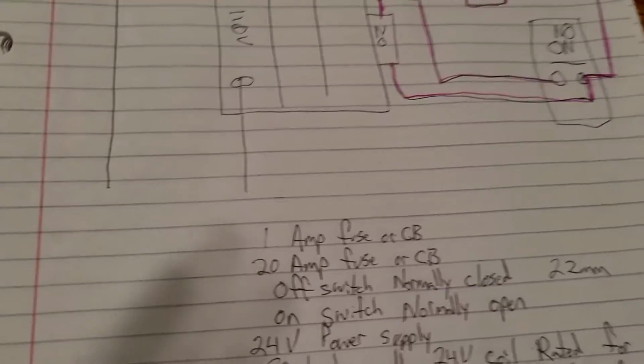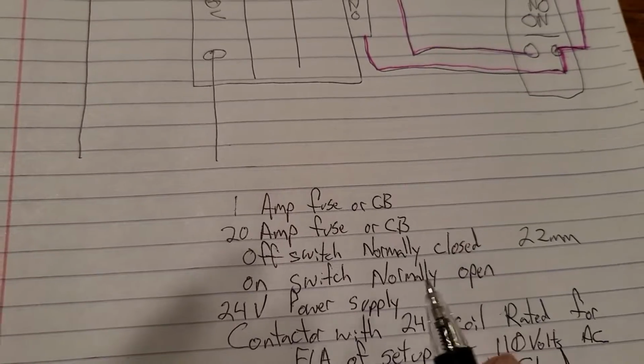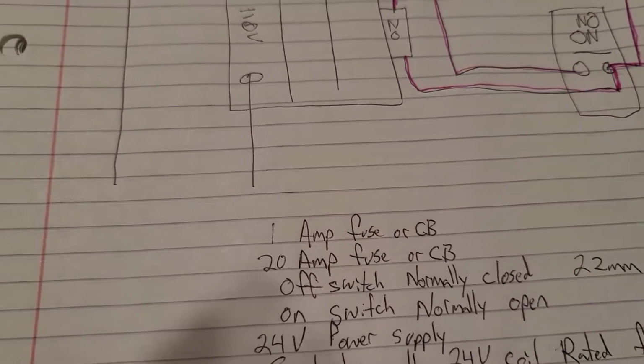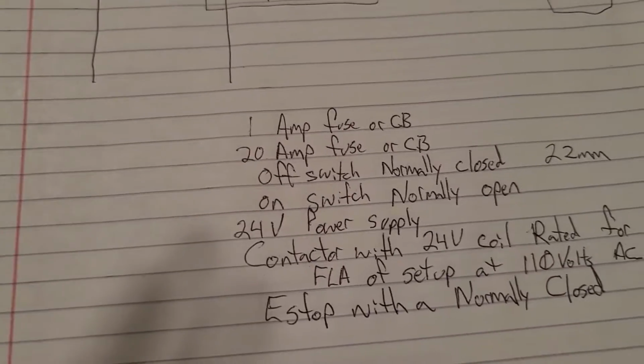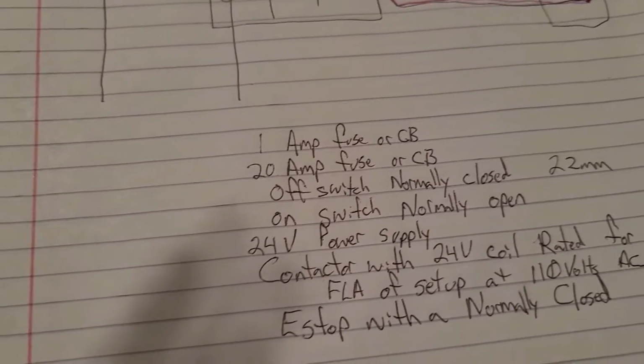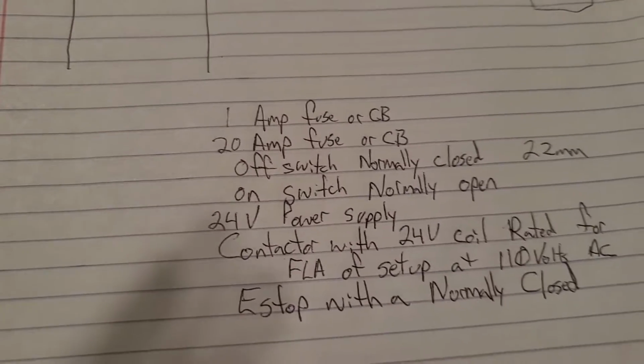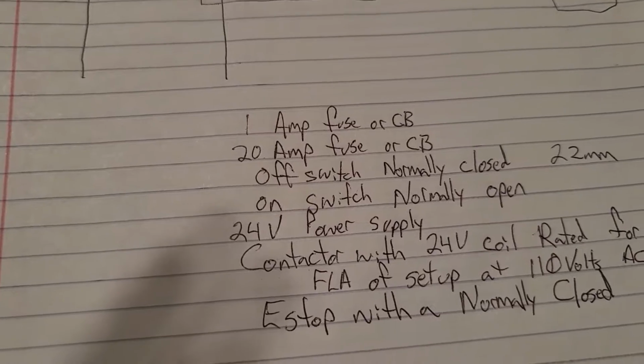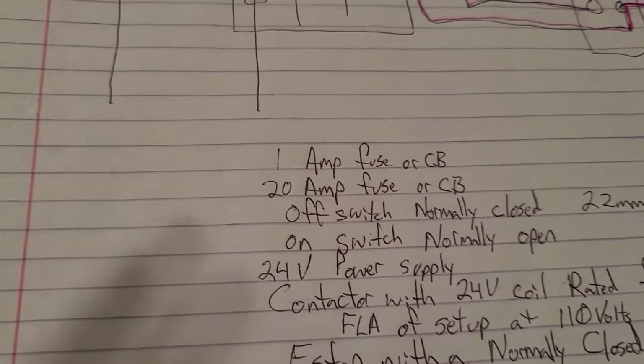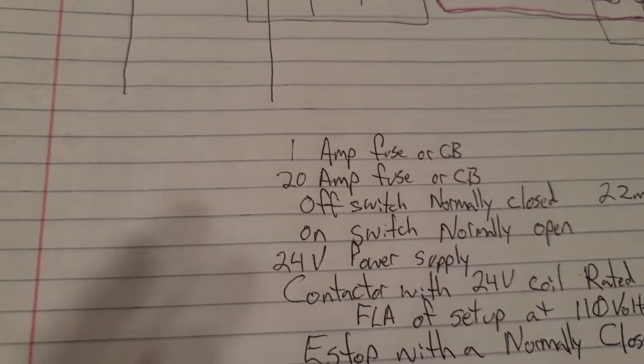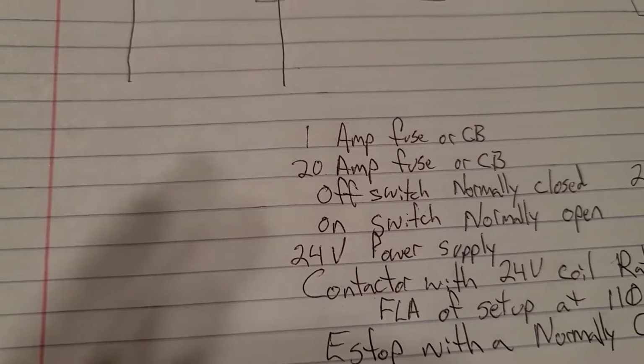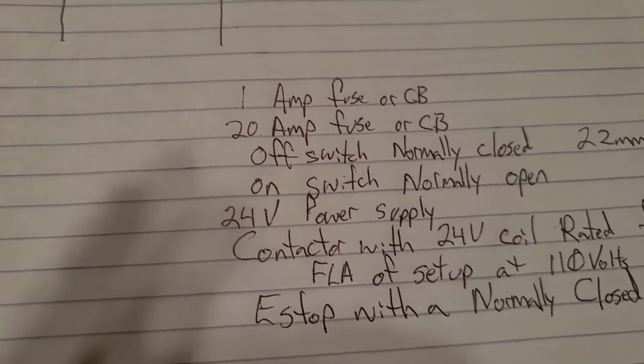And then you need an on switch, and you want it to be a normally open contact. So sometimes when you buy switches, if you buy them from WEG or somebody like that, you buy the button, and then you buy the contacts that you connect to the button. So for your off switch, you're going to have normally closed, and for the on switch, it's going to be normally open. And like I said, those are momentary, not latched.